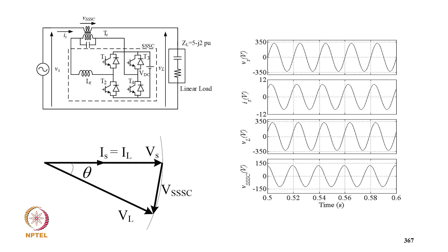So the solution is, given that the supply voltage Vs is 230 volt, 50 Hz, the critical load is ZL equal to 5 minus j2 per unit, and the base impedance is 6.9 ohm per phase. The load resistance is RL equal to 5 into 6.9, 34.5 ohm, and reactance is 2 into 6.9, that is 13.8 ohm. So total impedance is ZL equal to RL minus jX, that is Z at angle theta. Putting in values, it comes to 37.15 at the angle minus 21.8 ohm. The load current before compensation IL equal to VL upon ZL becomes 6.19, and the magnitude of supply current under compensation is equal to the load current, hence IS equal to IL equal to 6.19.